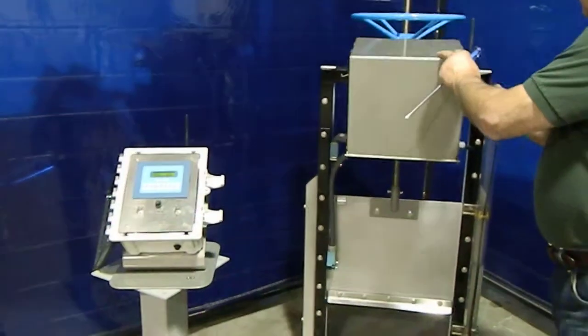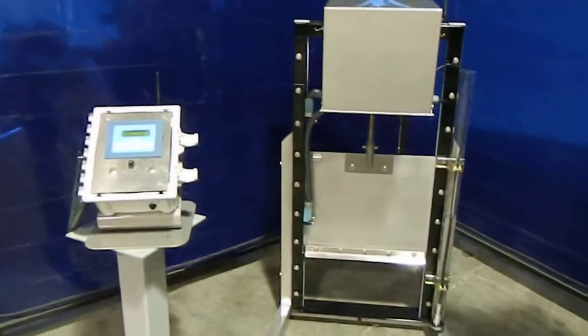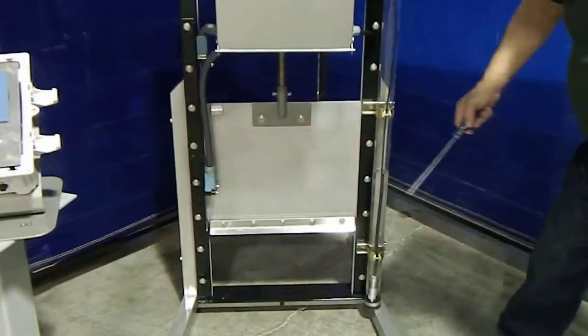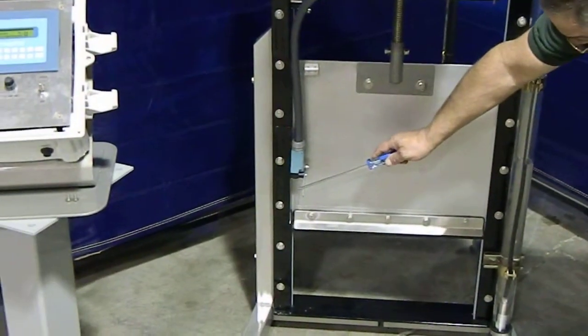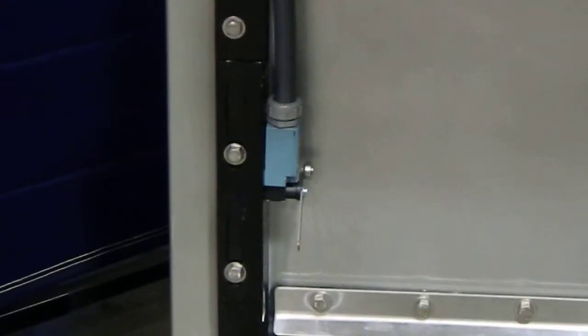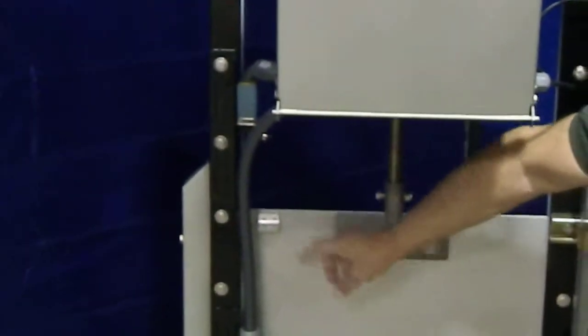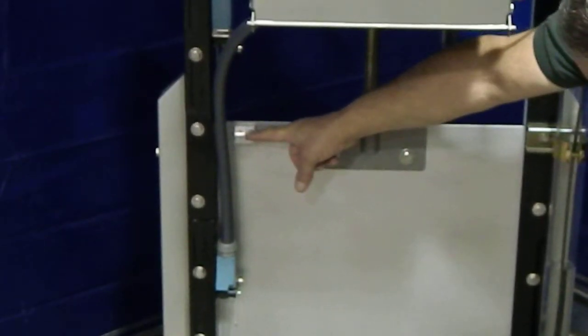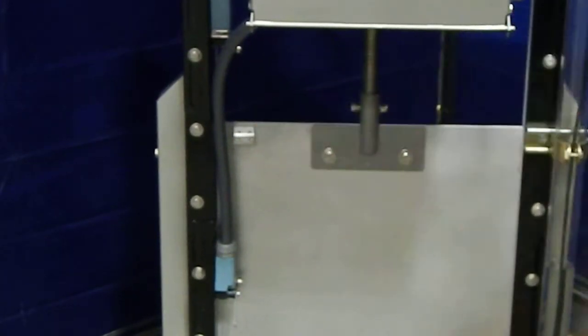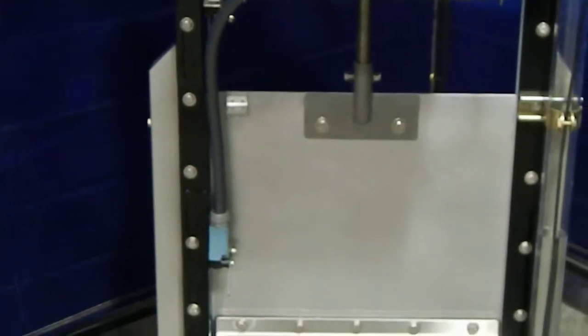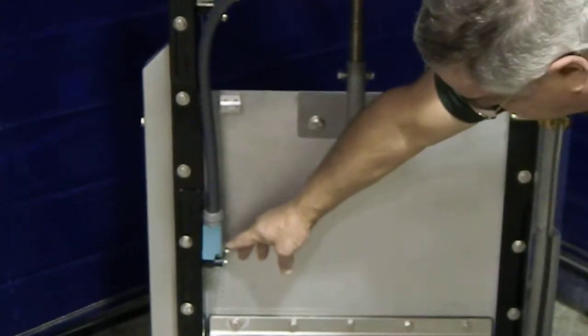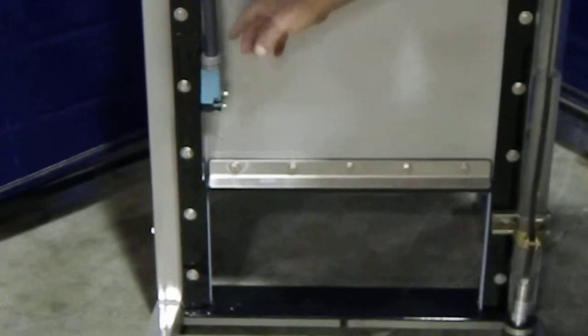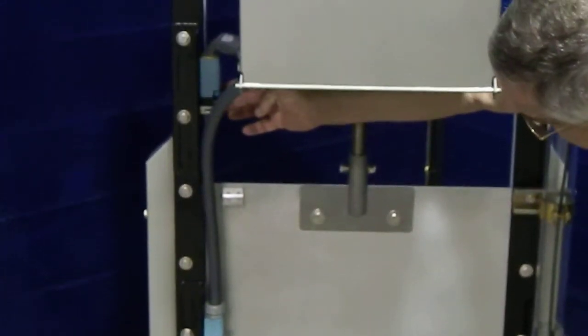I'm going to close this, point out a couple features of the gate. These blue units right here are your limit switches. When they are actuated, they stop the motor from moving in that direction. There's one on the bottom, one on the top. They're actuated by this little device right here, which is nothing more than a guide. When the gate gets low, that stops it. When it gets high, the upper one stops it.